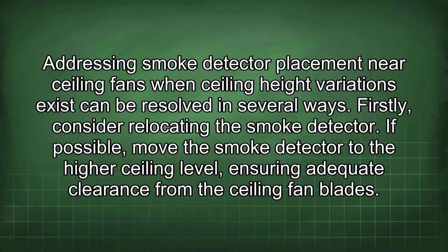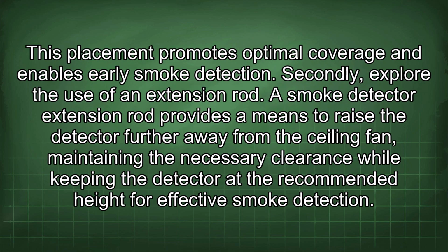Addressing smoke detector placement near ceiling fans when ceiling height variations exist can be resolved in several ways. Firstly, consider relocating the smoke detector. If possible, move the smoke detector to the higher ceiling level, ensuring adequate clearance from the ceiling fan blades. This placement promotes optimal coverage and enables early smoke detection.